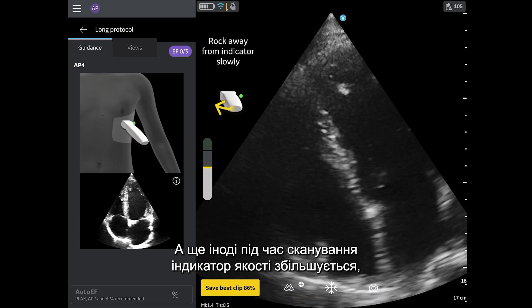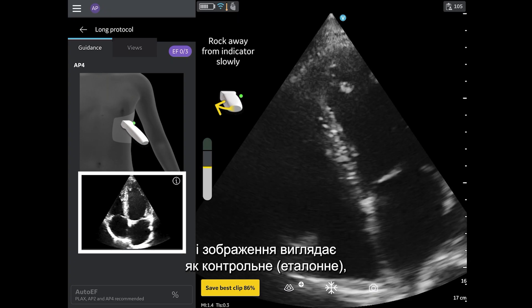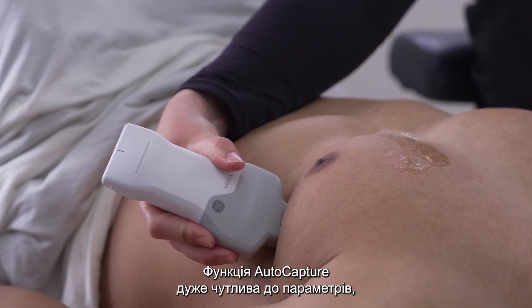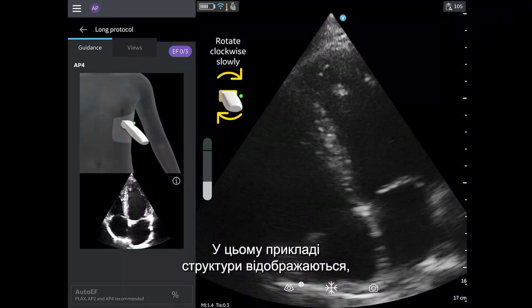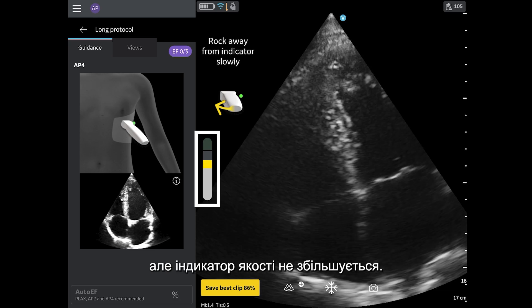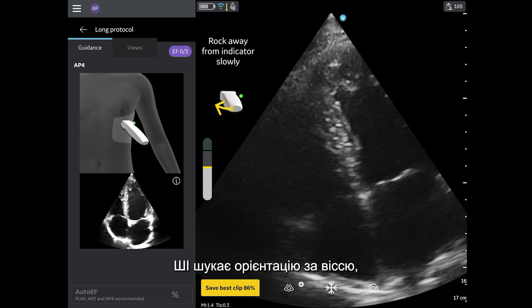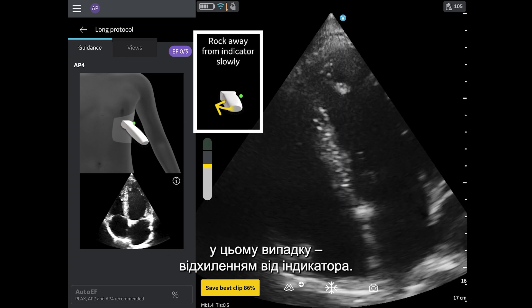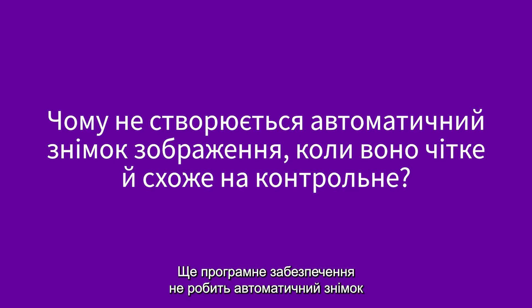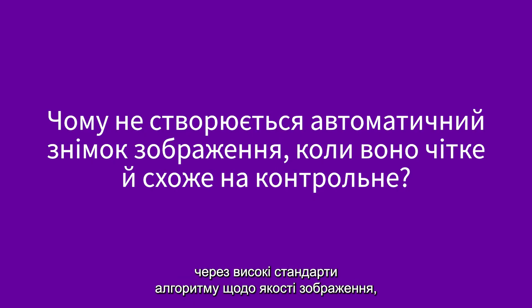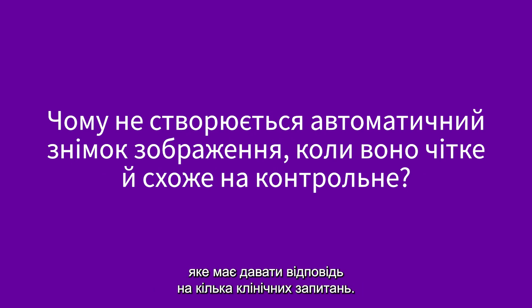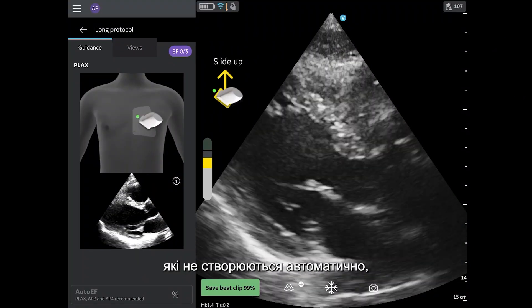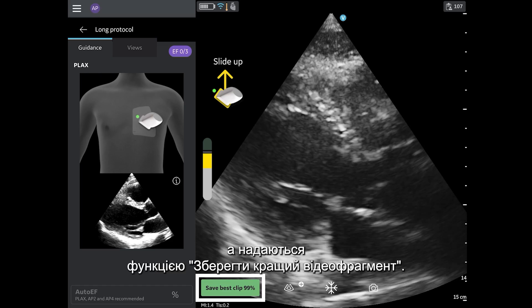Two, sometimes when scanning the quality meter will rise and the image looks like the reference image, but the image is not auto-capturing. The auto-capture feature is highly sensitive to parameters such as depth and on-axis orientation. In this example, you can see that the structures are visible, but the quality meter is not going up. The AI is looking for on-axis orientation, which can be achieved by following the prescriptive guidance — rocking away from the indicator in this case. Another reason why the software may not be auto-capturing is due to the high standards the algorithm places on image quality to allow for multiple clinical questions to be answered. However, often these clinical questions can be answered with images that do not auto-capture, but instead are saved using Save Best Clip.